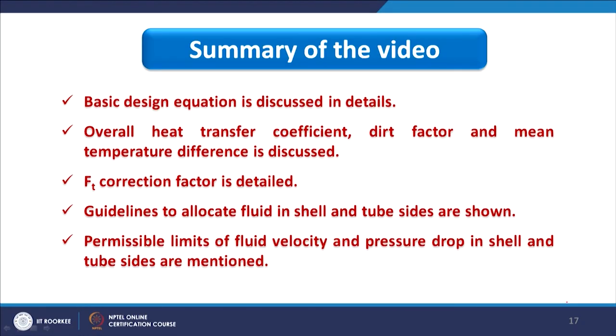These are the guidelines for shell and tube heat exchanger design. References are provided for detailed study of basic design parameters. In summary, these two lectures covered: the basic design equation (Q = U·A·ΔT_LM) in detail, overall heat transfer coefficient, dirt factor, mean temperature difference, FT correction factor, guidelines for fluid allocation to shell and tube side, and permissible limits for fluid velocity and pressure drop. That is all for this lecture. Thank you.